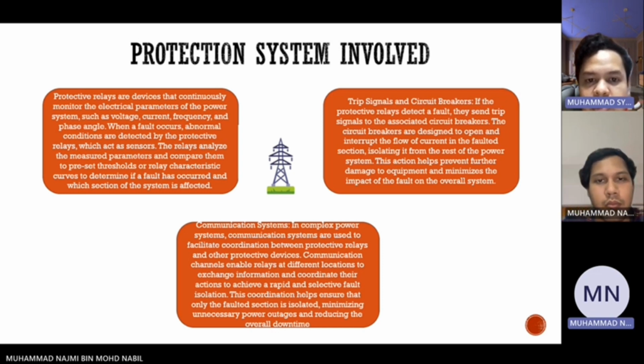And lastly, the communication system. In a complex power system, communication systems are used to facilitate coordination between protective relays and other protective devices. Communication channels enable relays at different locations to exchange information and coordinate their actions to achieve rapid, selective fault isolation. This coordination helps ensure that only the fault section is isolated, minimizing unnecessary power outages and reducing the overall downtime.